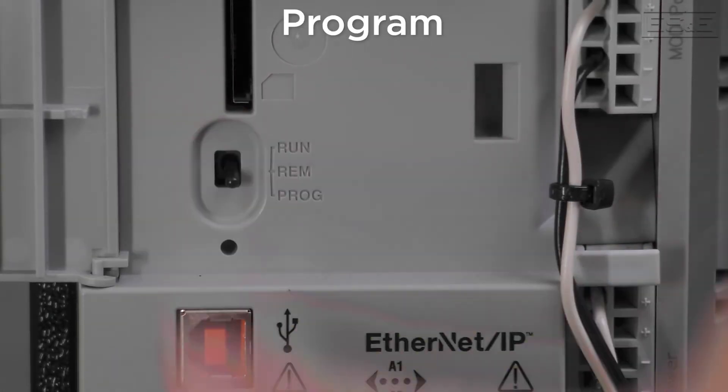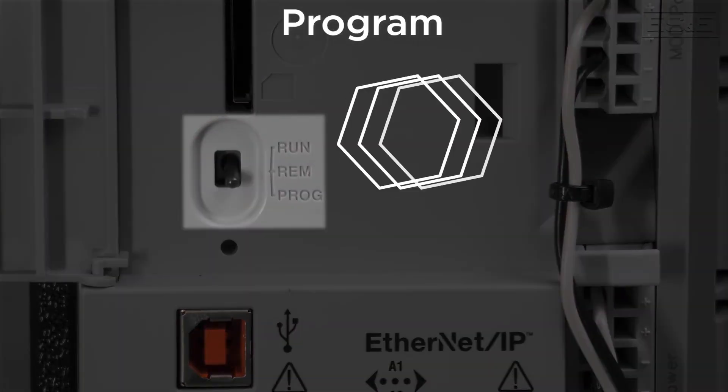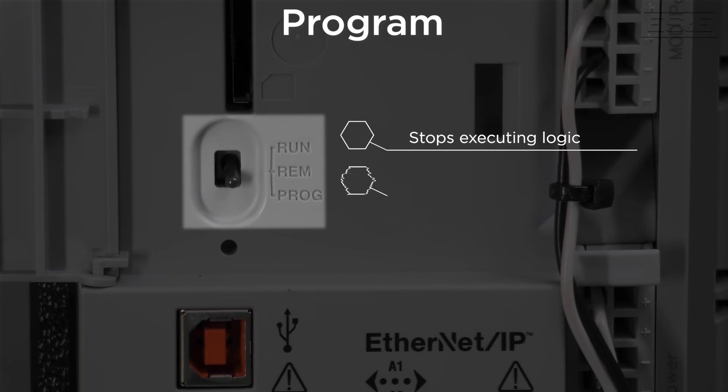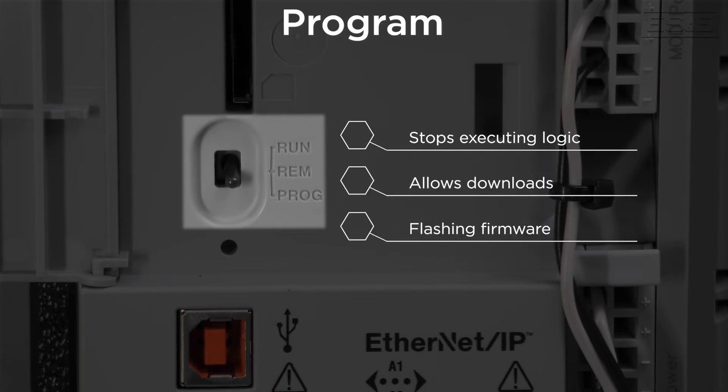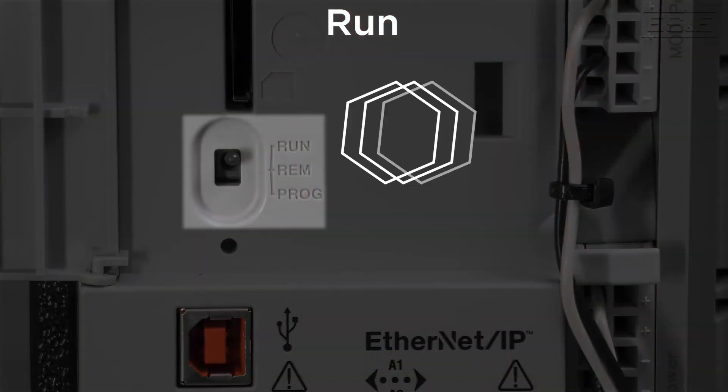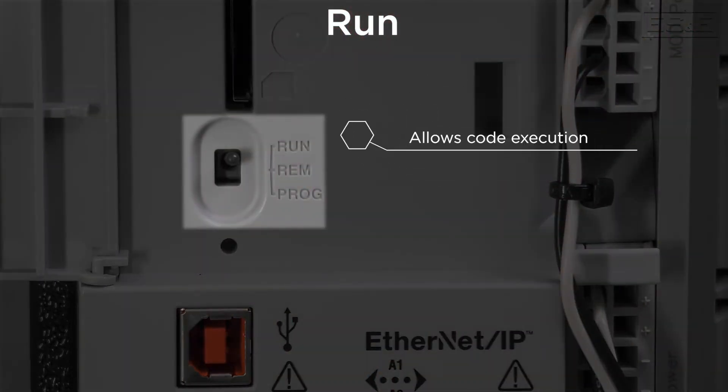Program mode stops the controller from executing the logic and allows downloads, but it is also necessary when flashing firmware or writing to non-volatile memory. Run mode allows the controller to execute the code, but prevents any editing or downloads.